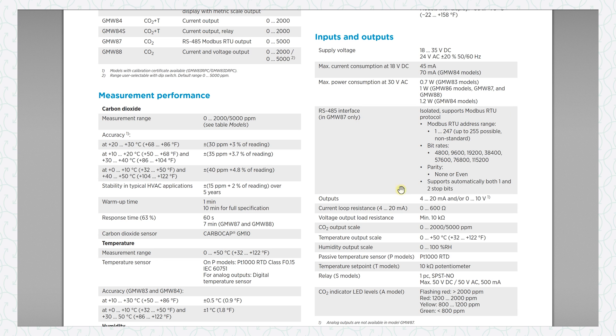This particular sensor can be purchased with RS485 Modbus RTU, 4 to 20 milliamp, or 0 to 10 volt output, so I'll definitely comment asking you to confirm which signal type you're providing. Also, for two-wire passive temperature sensors there's normally a selection between sensing elements — 1000 ohm, 10,000 ohm, nickel, platinum, and so on. In my specification the 1000 ohm is not compliant; the minimum is 10,000 ohm. If you don't tell me which one you're buying, I'm going to flag it.